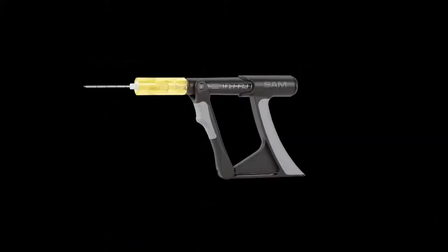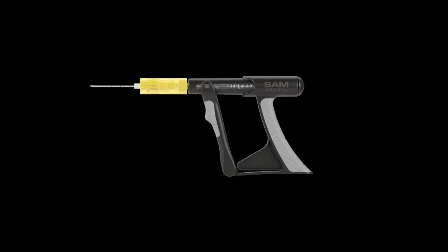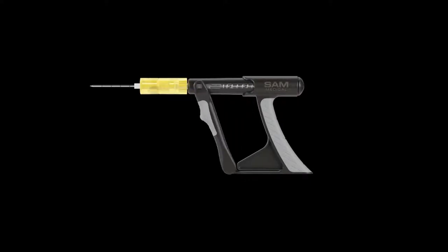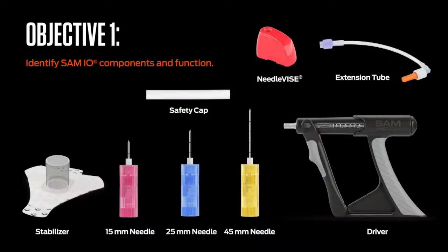The SAM.IO is a manually operated interosseous access system. Catheter placement is achieved by continuously actuating — repeatedly compressing — the driver's trigger assembly while gently guiding the needle assembly into position. Repeated full-trigger actuation completes a rotational spin of the needle assembly which, when combined with gentle downward pressure, results in a controlled I.O. placement.